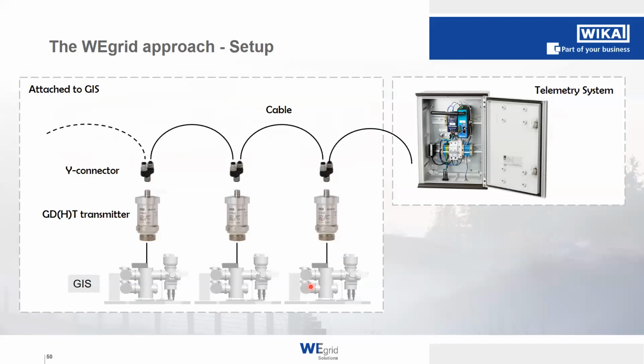What we are providing here is a complete system, basically. So you can see here our WEGrid approach. Let's take a look at the complete setup now. On each gas compartment, we do have a sensor, and each sensor is then connected via a Modbus line to the next sensor. So this is a Modbus line where we can connect a big amount of sensors together.